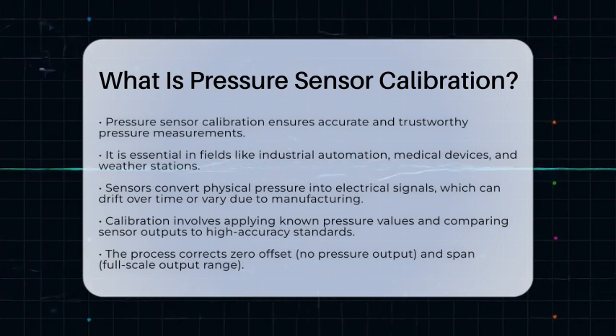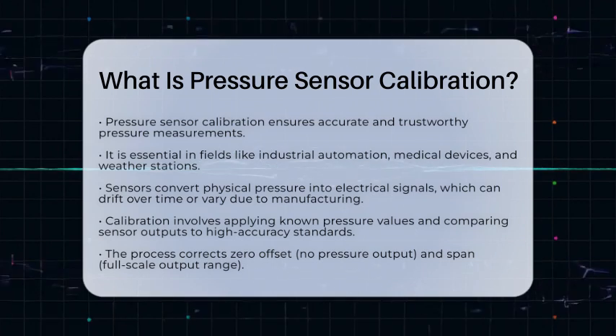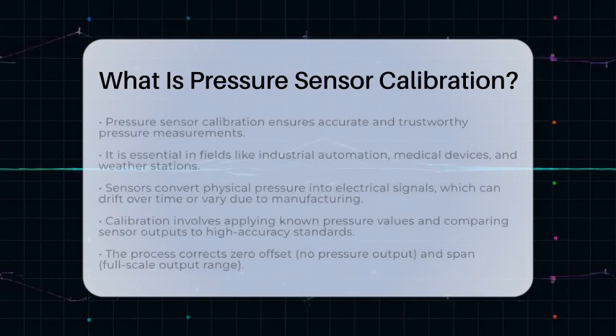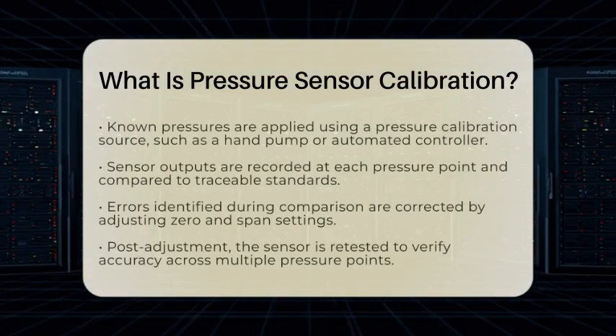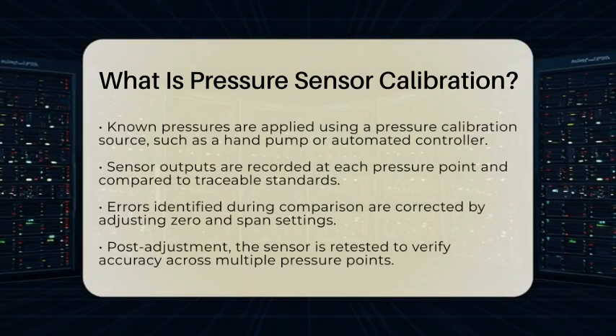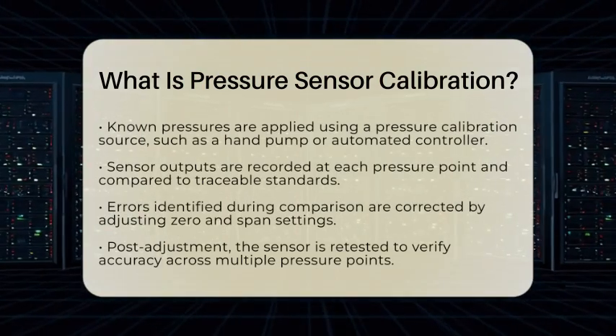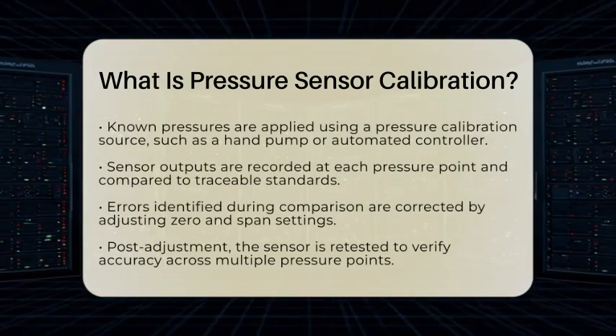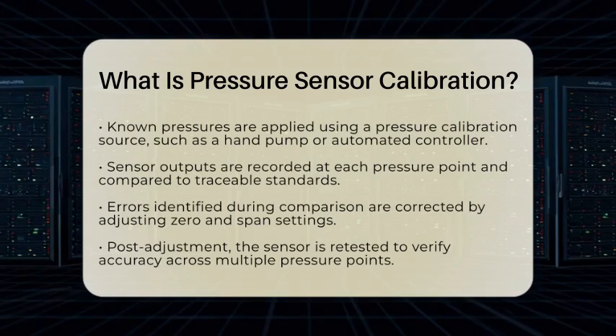Calibration helps fix that. It involves applying known pressure values to the sensor and comparing its electrical output to those standards. If the sensor's readings are off, adjustments are made to correct the zero offset, which is the output when no pressure is applied, and the span, which is the full-scale output range.